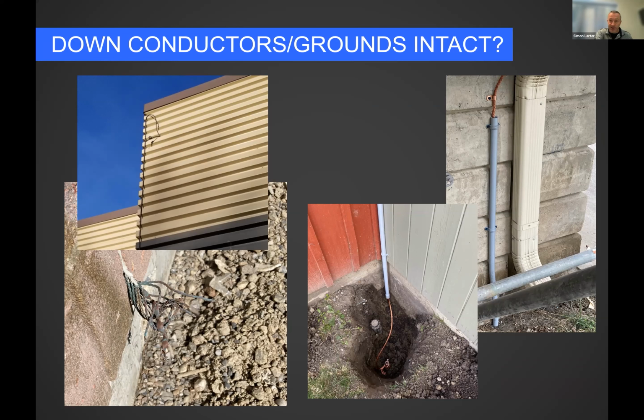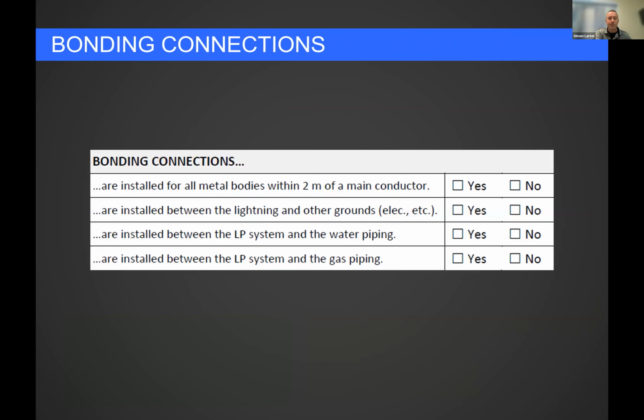There's no way you can inspect that, but that's why we have qualified installers and good electricians, and we keep records and we take photographs. So you won't be able to inspect it, but you should be able to interface with the installer or the electrician or whoever took care of the down conductors and confirm with them that it was done. They'll have photographs and stuff. We need to be able to prove it to certify our systems. So we try and keep good records about that.